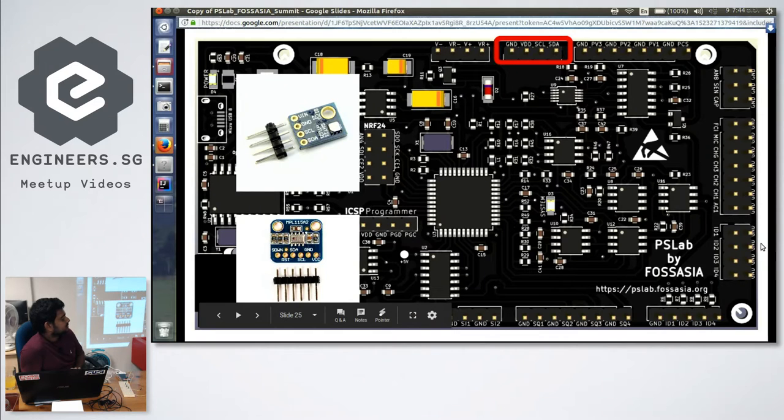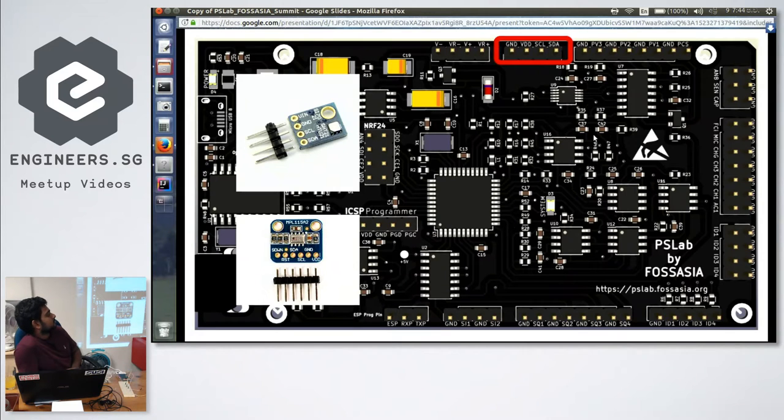For your scope, do you have filtering inside, on input and output? Or just the waveform coming directly in the input? Directly, and it will amplify according to the setting we choose. It's between minus 16 and plus 16, or plus 5 to minus 5. Go to the amplitude resolution range, it will show the gain.